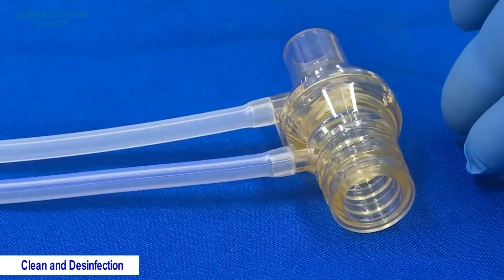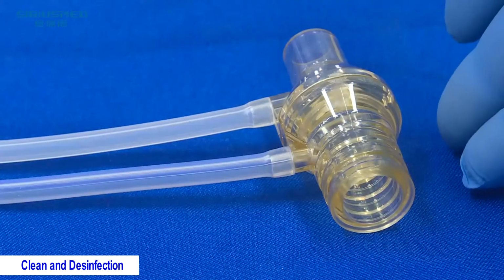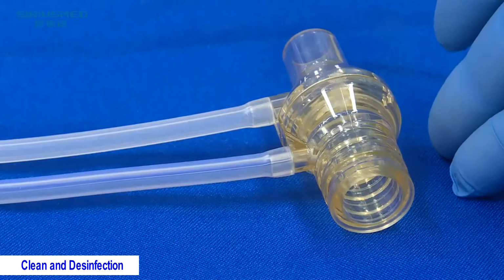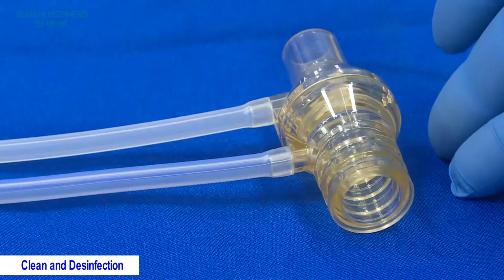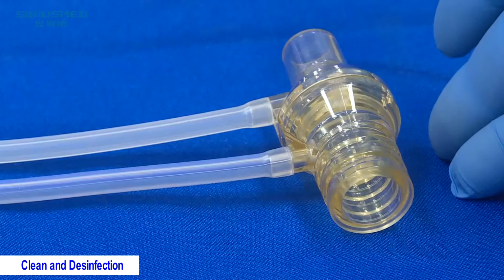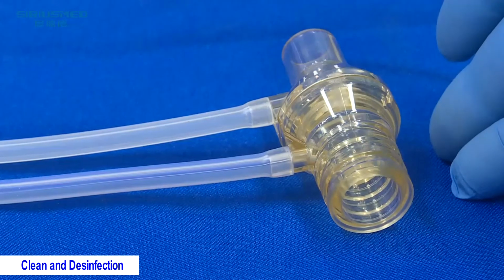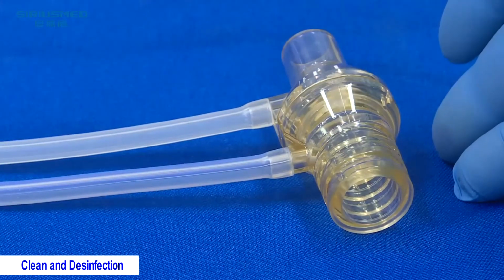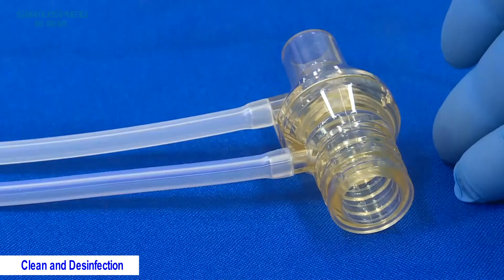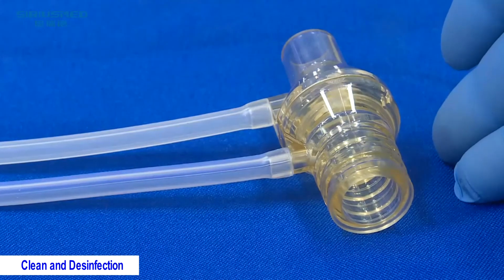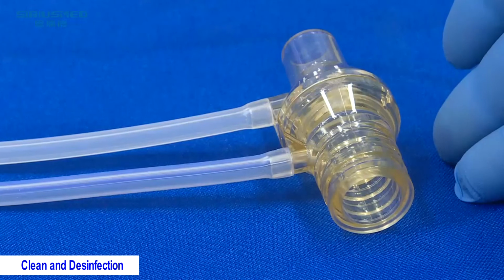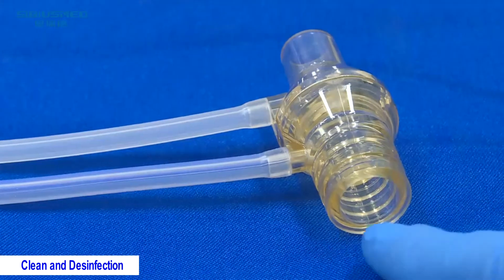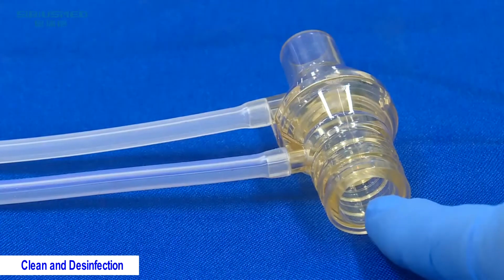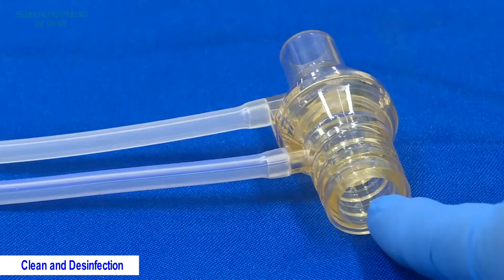For this flow sensor probe, please pay attention to the tubes: the flow sensor sampling tube can also be autoclaved in high pressure and high temperature. And pay attention to the probe inside. It cannot be flushed with water or other high pressure. If anything inside is damaged, it cannot be used normally.